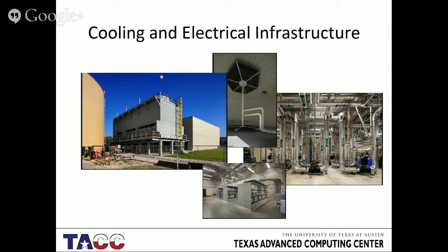Here's a picture of the infrastructure that they built. So what you see over here, this is the pump room. See all the pipes? There are 3 pumps. There's usually 2 pumps running and 1 pump down for maintenance and also a standby. This is the power room, a lot of the breaker switches and the transformers. Here are the chillers. You may be wondering what's this in the middle, this strange looking room. That's the inside of this tank over here to the left.